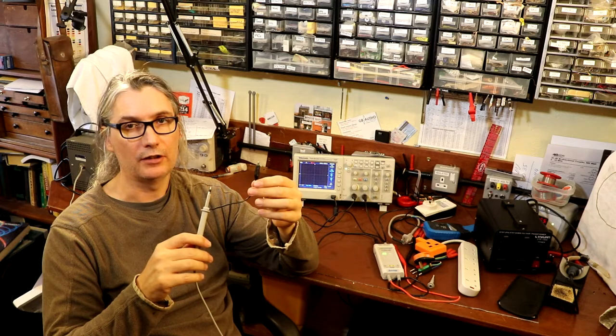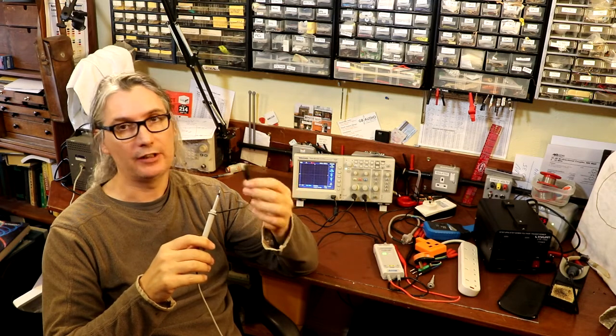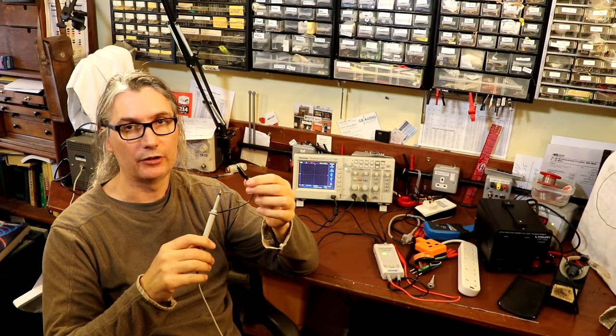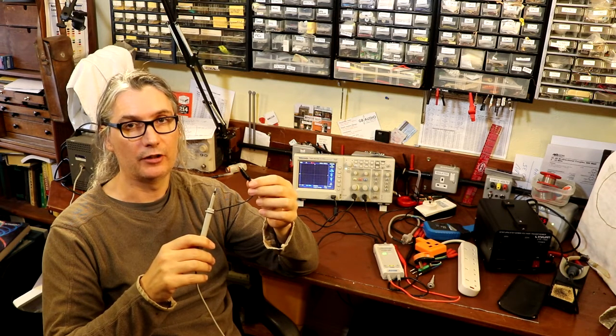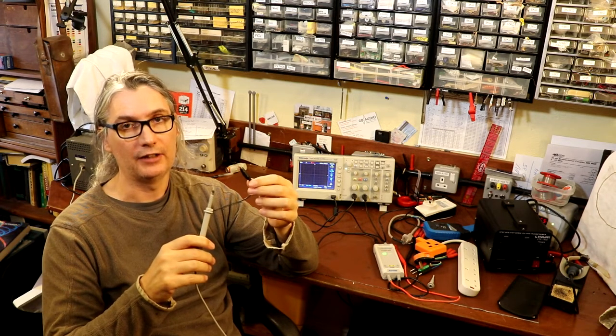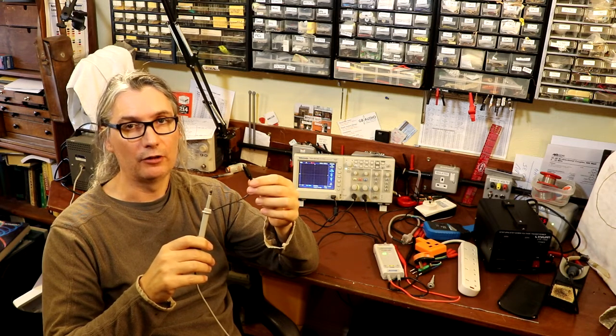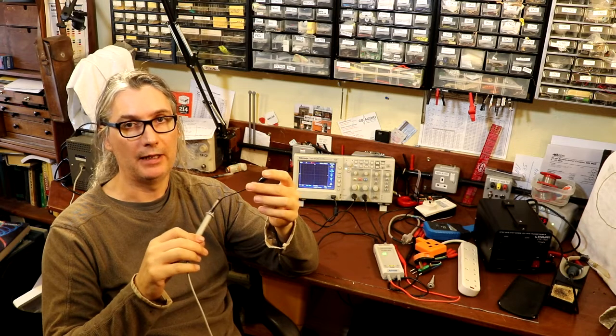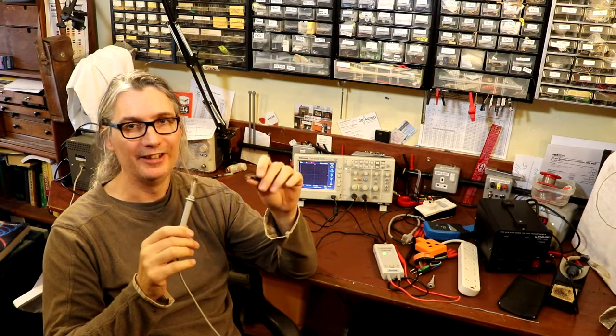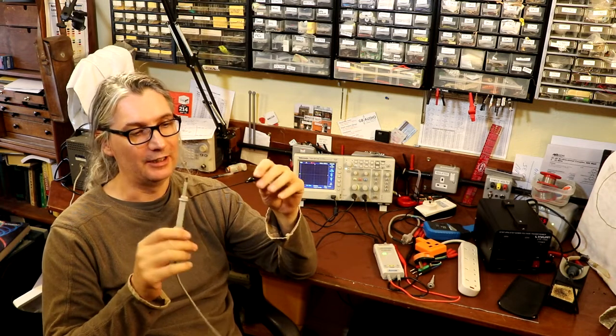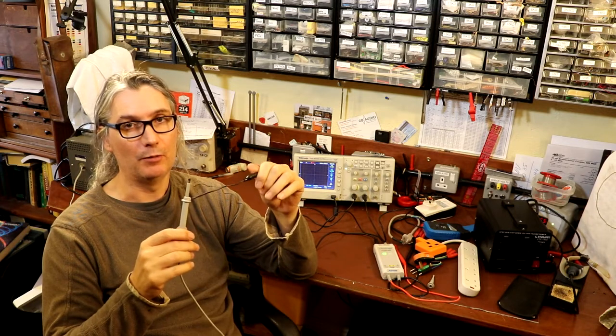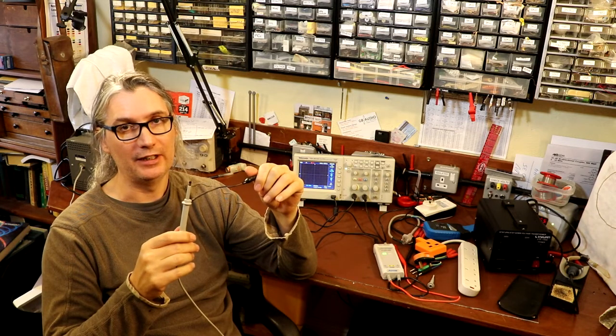That can cause a problem, because if you clip this onto a live part of your circuit, say the live supply, you're putting a direct short circuit between the live supply and your earth. If you're lucky you'll just get a big bang, the power will go off, and you'll probably end up frying the earth connection on your scope. I'd say most of us have done it at one point or another — well, you have if you've been in industry long enough.